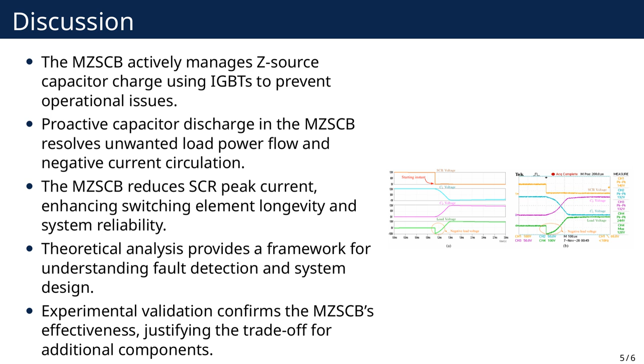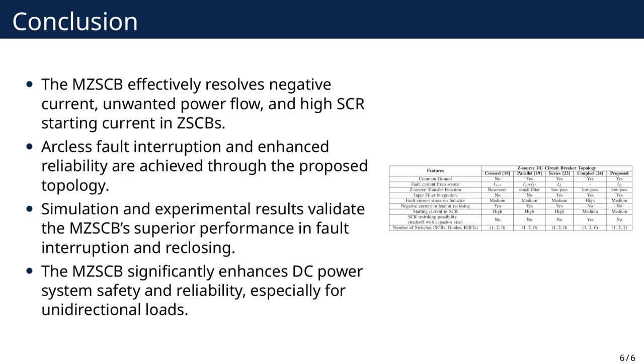This article has presented a modified Z-source DC circuit breaker, MZ-SCB, designed to overcome critical challenges in conventional Z-source DC circuit breakers. Specifically, the MZ-SCB effectively resolves issues of negative current circulation in the load during reclosing and commissioning, prevents unwanted power flow to the load during commissioning, and reduces the high starting current experienced by the main SCR during reclosing and commissioning.